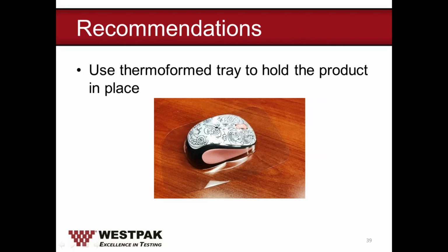So by this time, we said, okay, are you really keeping your Tyvek pouch? And him and his manager, his boss, agreed that they want to keep the Tyvek pouch. So our next recommendation is use the thermoform tray to hold the product in place. So here's our mouse again with the thermoform tray to prevent the product from rubbing against the Tyvek.